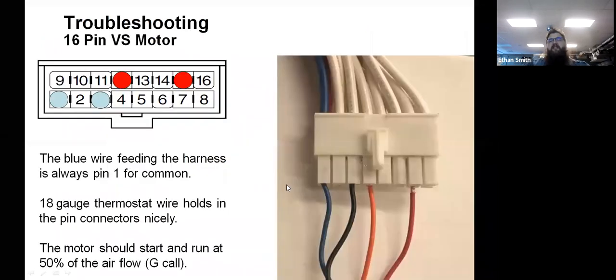The other thing to do is we can give this thing what's called a go, no go test. So this is that typical 16-pin harness that we see on these ECM 2.3s. You'll notice that there is a blue and an orange wire on one end. That is to denote terminal designations. So that blue wire is always going to be pin number 1. That orange wire is always going to be pin number 9. But if we feed 24 volt common into pins 1 and 3 and 24 volts hot into pins 12 and 15, we can actually get this motor to start. We're sending in an artificial call for G. And so that motor is going to run at 50% of cooling speed at that point.